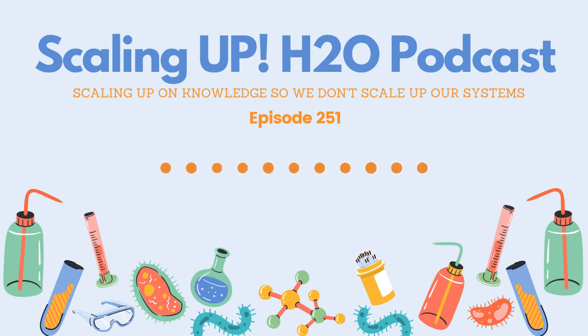And we never want to put water in there, because that can actually force the juice that's inside the probe to transmit outside of the probe, because nature loves balance and it's trying to balance the fact that there's more inside than there is outside. So don't do that. There's a reason that there's storage solutions out there. If you want to learn more about that, contact wherever you get your test equipment and supplies from. They will tell you all about that.